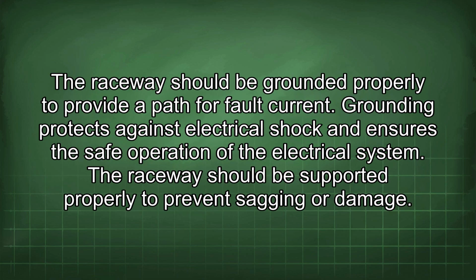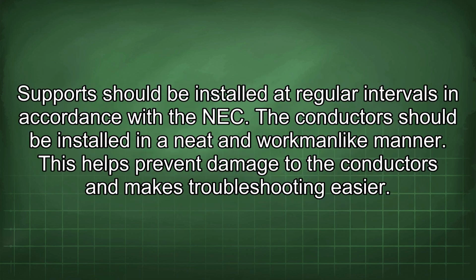The raceway should be grounded properly to provide a path for fault current. Grounding protects against electrical shock and ensures the safe operation of the electrical system. The raceway should be supported properly to prevent sagging or damage. Support should be installed at regular intervals in accordance with the NEC. The conductor should be installed in a neat and workmanlike manner. This helps prevent damage to the conductors and makes troubleshooting easier.